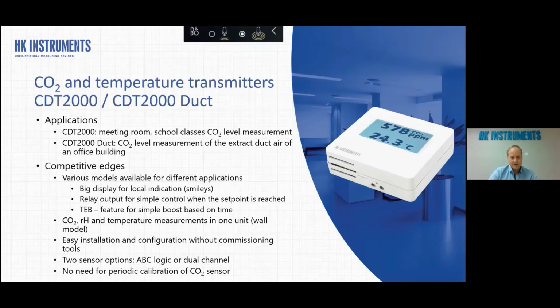And we added just maybe 1 month ago this new feature which we called TEB. It comes from the words time extension button. So basically the user can use the touchscreen and push it, it's like a clock. You just push it and you can select 1 hour, 2 hours, 4 hours or 8 hours, like this kind of extra boost ventilation. When you press it on, the relay will snap and ask the control device to put more air into the room.